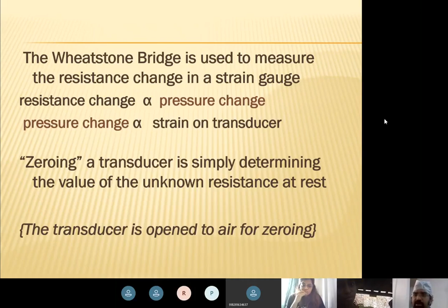All right. Now the other thing is a small transducer which you're going to zero. That blue colored thing is a small transducer that you're going to zero. You understand how to zero it now, right? Open the transducer to the atmospheric pressure. That is zeroing. And press the zero button on the monitor. That is the meaning of zeroing. Clear on this?